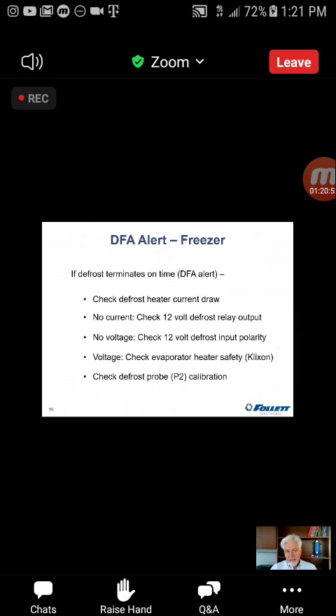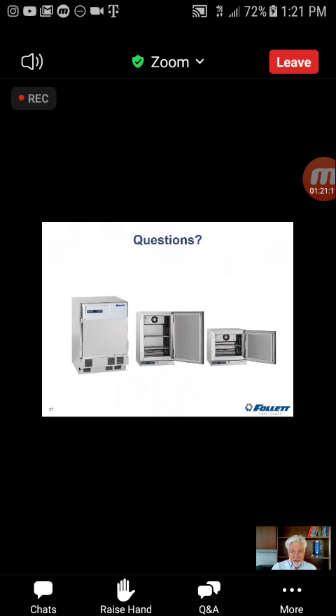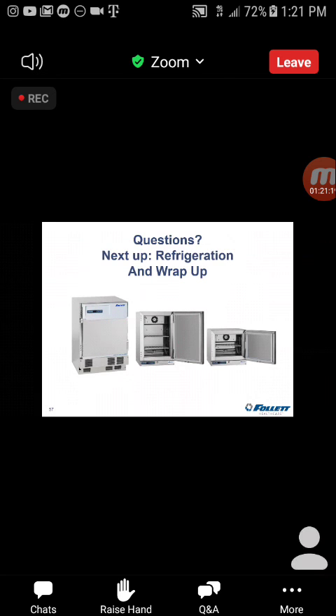And then finally, the last thing that we do, if all of that looks good, let's check the probe itself. Maybe the probe is lying to us. We've already gone over the 5 degrees, but the probe is not telling the board that, so we may need to validate the defrost termination probe. So that's the process for doing that. All right. Any questions on anything we've covered so far? Well, that's one more thing to go. I didn't get myself unmuted. Any questions? So I'm going to begin then to unmute the audio.